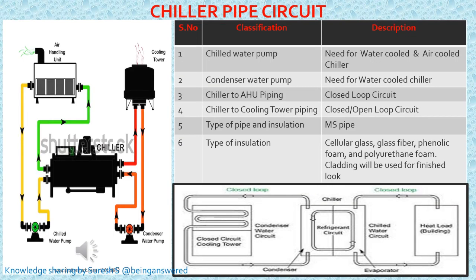Here you are seeing the chiller pipe circuit. There is a unit called the air handling unit mentioned. You can see the chiller, the chilled water pump and the condenser water pump mentioned, and above, the cooling tower. The chilled water pump is needed for all types of chillers, because that is the pump which supplies the water in the chilled circuit from the chiller to the AHU room. The condenser water pump is needed only for the water cooled chiller. The chiller to AHU piping will be a closed loop circuit. The chiller to cooling tower piping will be closed; it may be open also.